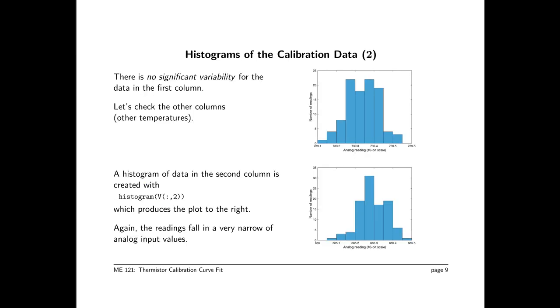This slide shows the first column histogram and the second column histogram. The lower plot is obtained with histogram v colon comma 2. The colon again is the wildcard. Now 2 indicates the second column. And that histogram also has a central tendency, which is good. And all the values are in a very narrow range, 665 to 665.5. It turns out that the data set that I have here has an extremely well behaved set of analog input readings for the calibration data.